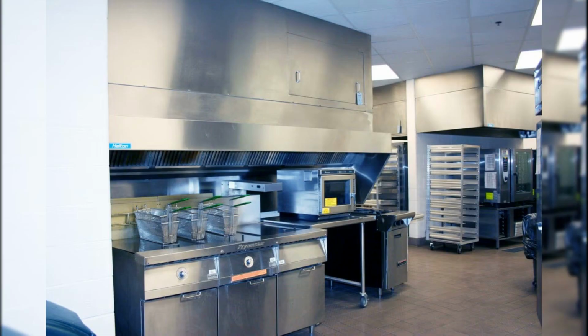Kitchen: 72 degrees Fahrenheit winter, 82 degrees Fahrenheit summer for Case 1, or 78 degrees Fahrenheit summer for Case 2. Cafeteria: 72 degrees Fahrenheit winter, 78 degrees Fahrenheit summer. All hoods need FDNY performance testing and inspection approval. Exhaust outlets must be at least 10 feet away from intakes.